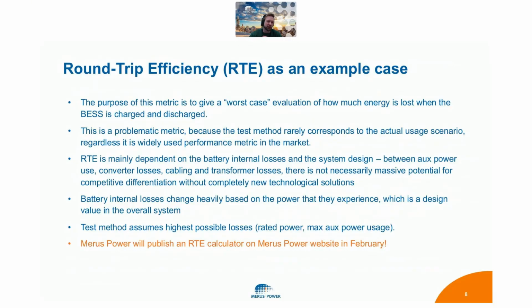But if you look at how this is actually measured, it defines the worst case point of operation and assumes that you charge and discharge the battery at full power all the time. If you change the charging and discharging power, the RTE always changes in some direction.